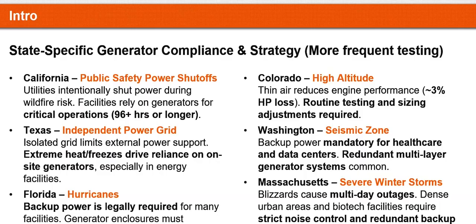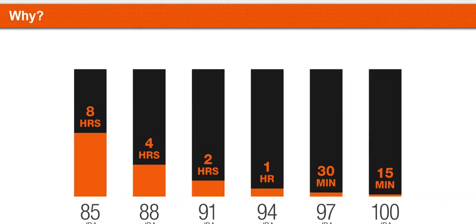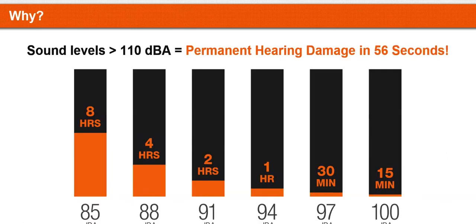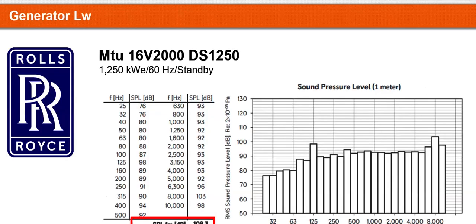And the reason, and this is important to take into account, is when you're emitting sound at 120 decibels plus from these pieces of equipment, you could generate hearing loss, permanent hearing damage, in less than a minute. And that is extremely dangerous. You could open yourself to a lawsuit. As an example of a generator, I have a nice Rolls Royce here, a 1200 kilowatt standby emergency generator on a project that I'm working on in Miami.